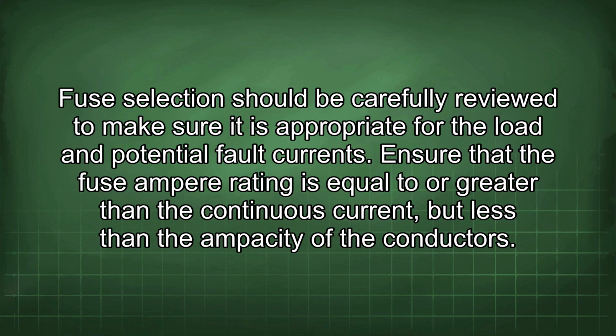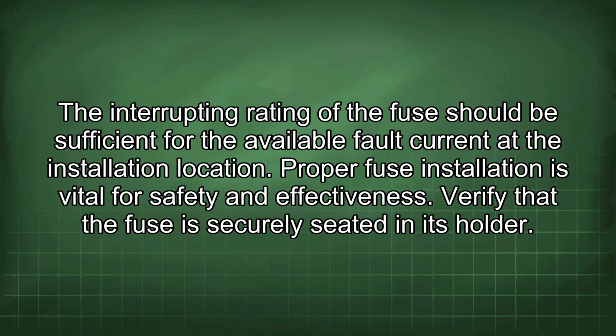Fuse selection should be carefully reviewed to make sure it is appropriate for the load and potential fault currents. Ensure that the fuse ampere rating is equal to or greater than the continuous current, but less than the ampacity of the conductors. The interrupting rating of the fuse should be sufficient for the available fault current at the installation location. Proper fuse installation is vital for safety and effectiveness.